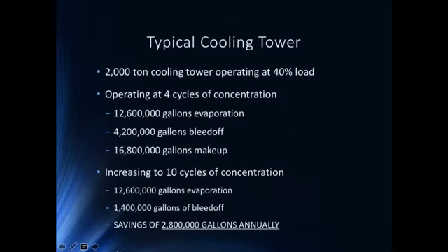So let's talk a little bit about how much water we're talking about. Essentially, if we look at a typical 2,000-ton cooling tower operating at 40% load, kind of an average in Southern California as far as a high-rise building or a smaller hospital. And let's say we're running 4 cycles of concentration, and that's very typical of what most chemical water treatment companies are running in the Southern California area. Some lower, some higher, but this will give us perspective of the ballpark of water we're talking about. In that 2,000-ton cooling tower at 40% load, we're going to evaporate 12.6 million gallons a year. So 12.6 million gallons of water is used from an evaporation standpoint out of that tower to remove the heat load from the building.